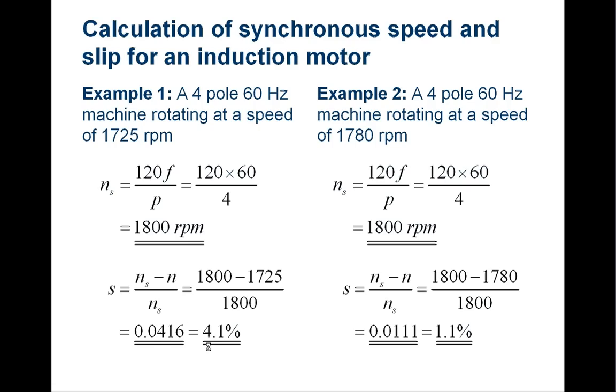Similarly, a four-pole 60 Hz machine rotating at 1780 RPM will result in a slip of 0.0111, which is about 1.1%.